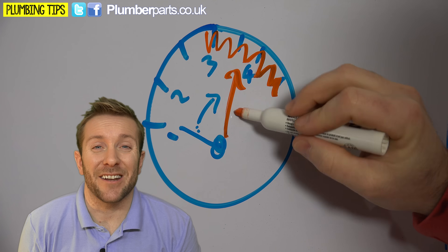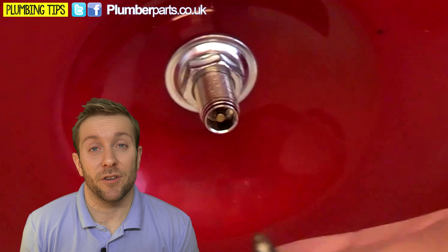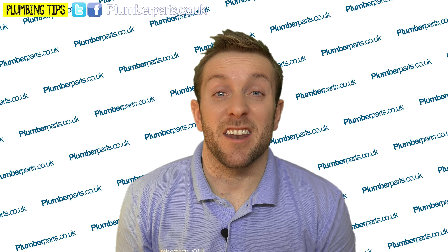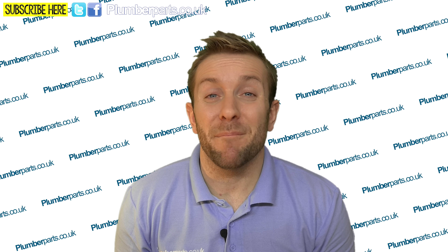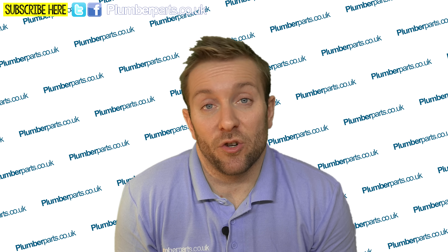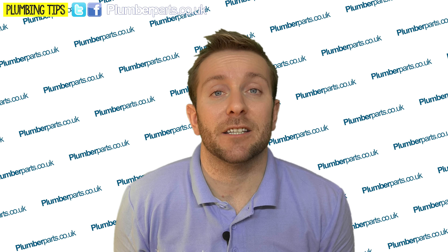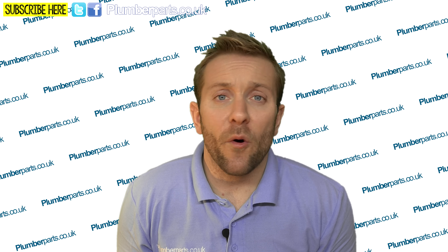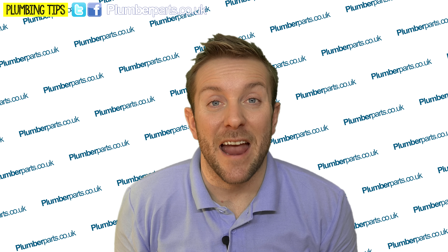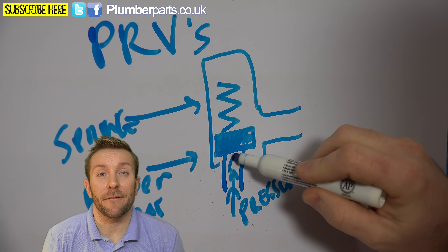What will happen is the system pressure will go up and up and actually force the pressure relief valve to open. To check if you've got a problem with your expansion vessel, find what looks like a bike pump connector on the top or side, press that, and if water starts to come out, that's a bad thing and you'll need to put a new expansion vessel on. If no water comes out, it might have just lost its charge through that Schrader valve — you can get a bicycle pump and re-pressurize it, using a pressure gauge to make sure it's pumped up to one or one and a half bar. Also note that a lot of combi boilers only have an expansion vessel that accounts for the expansion of the boiler itself. If your plumber is putting a new boiler in, ask him to add a remote expansion vessel somewhere else on the heating system — usually in the airing cupboard — and you'll halve the risk of any problem with the expansion vessel or pressure relief valve because you've got so much more expansion space.